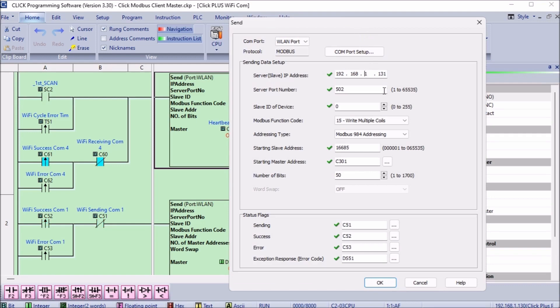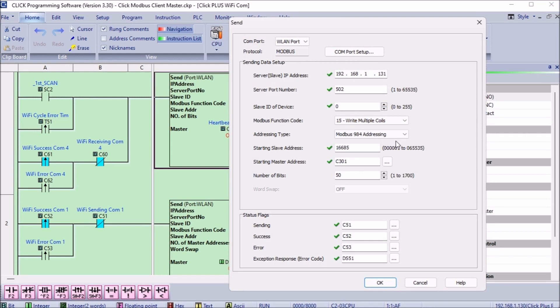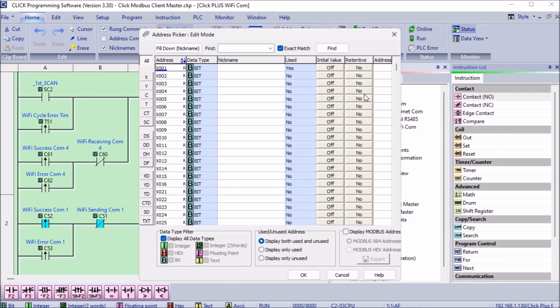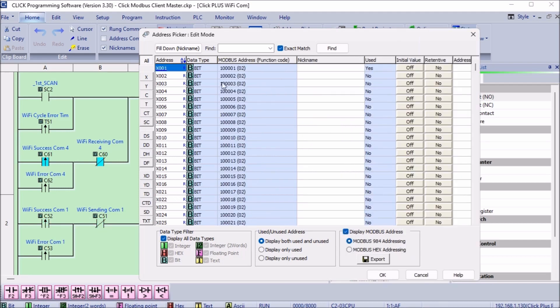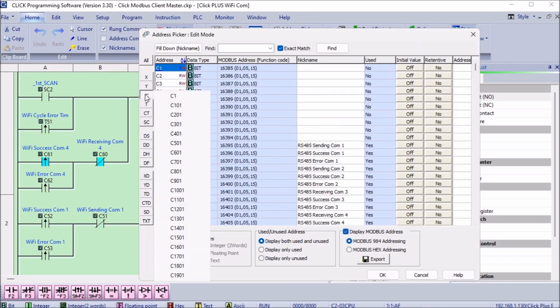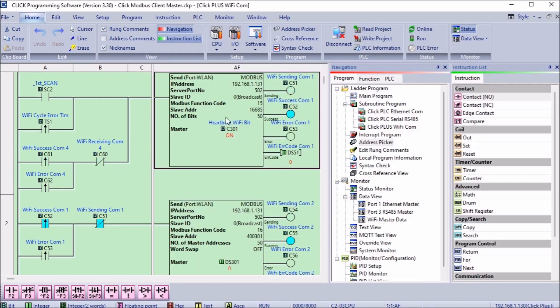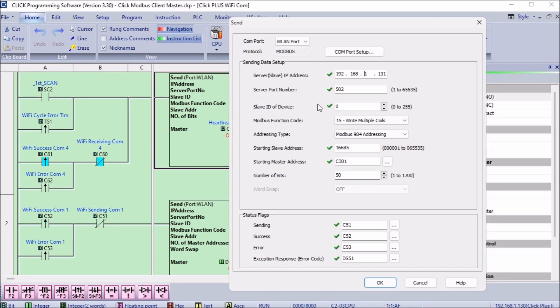The Modbus function code is set for 15. This is used to write multiple coils. Our address type is set up for Modbus 984 addressing and the starting slave address is 16685. The starting client address is C301. Call up the address picker from the main menu program. Select the slave Modbus address in the bottom right side of the address picker window. This will display the Modbus addresses of all the memory locations in the CLICK PLC. 16685 is the address for C301. Looking back at the send instruction, we are sending 50 bits. This means that bits C301 to C350 from the client PLC are being sent to bits C301 to C350 of the server PLC.